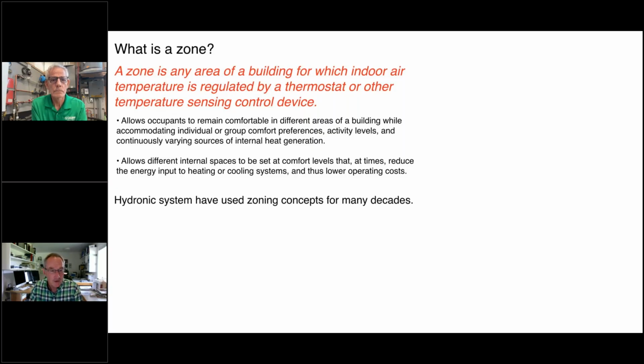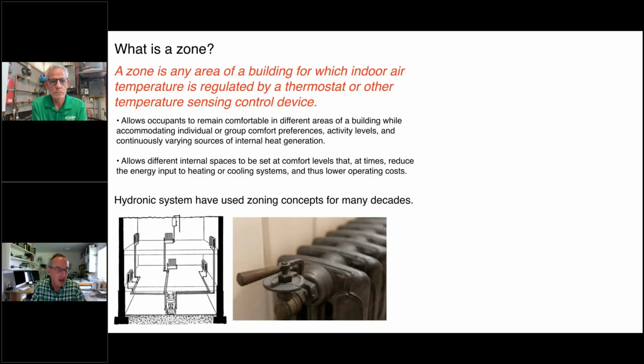And hydronic systems have used the concept of zoning for decades. And just an example, here's a system, the drawing down there on the lower left, that actually goes back into the very early 1900s. You won't see a circulator in that system because circulators hadn't been used yet. Electric motors weren't around yet. That was what we often call a gravity system.